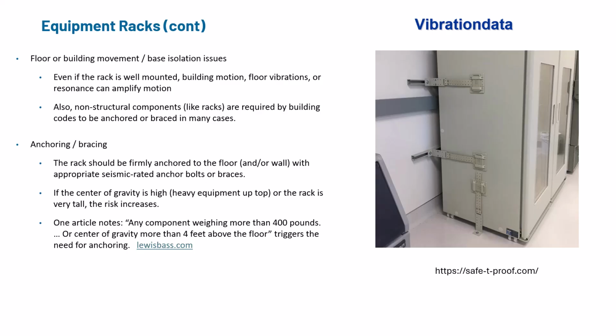So what kind of force, and what is the base shear force, how is that force distributed up and down that rack, and the overturning moments, etc. We will be addressing that later on, equations and so forth. So these non-structural components like racks are required by building codes to be anchored or braced in many cases. It's just also common sense regardless of what the requirement might be. The rack should be firmly anchored to the floor and or walls with appropriate seismic rated anchor bolts or braces.